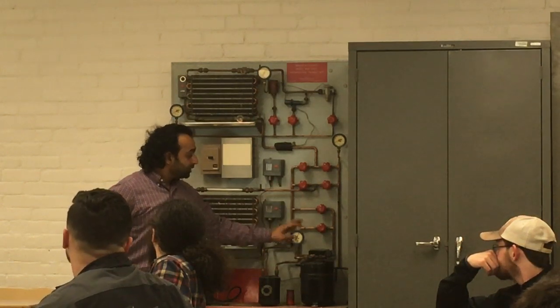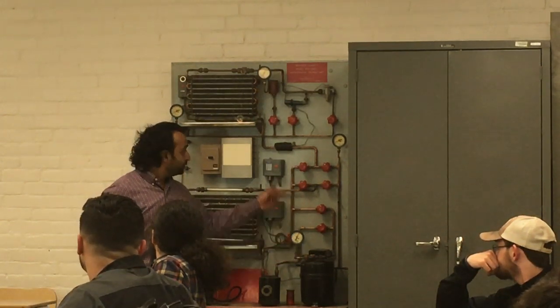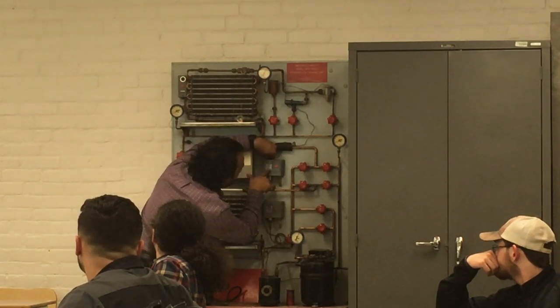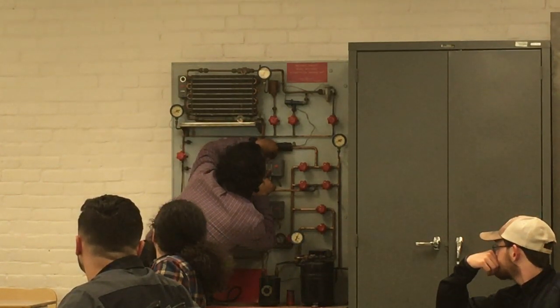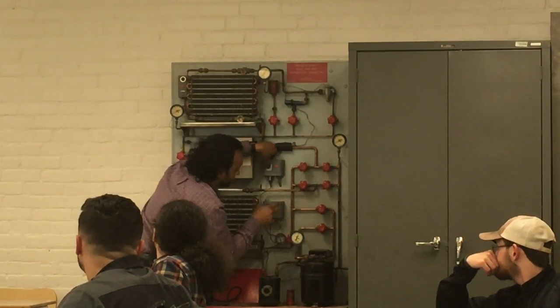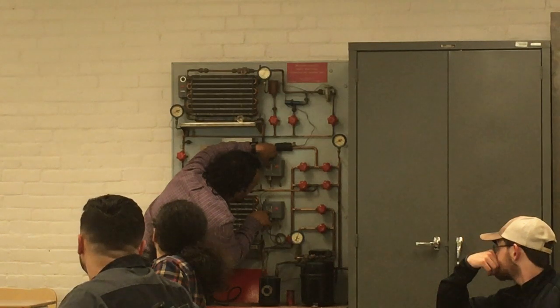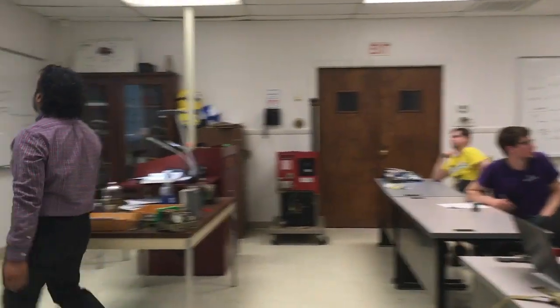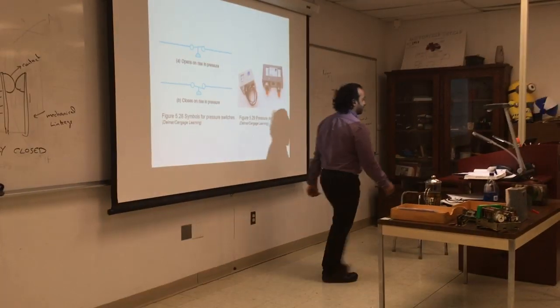This will disengage the compressor if you reach the high pressure or low pressure, and you can set that with a screwdriver. So this high pressure is set at 250 psi. It will shut off the system. This for low pressure. If it runs at low pressure minus 20, which is vacuum, it will shut off the compressor. Otherwise, the compressor will malfunction. So those are put for what? For safety. So safety switches, and you also find those in power plant.